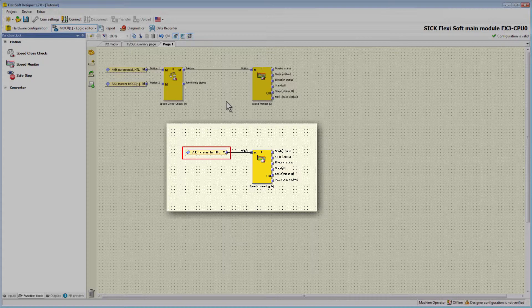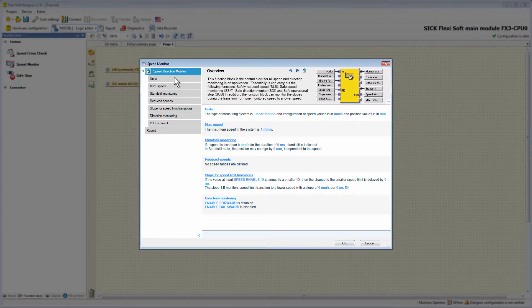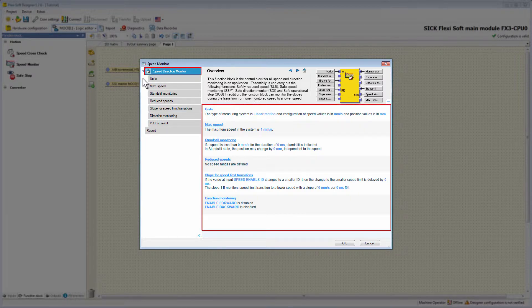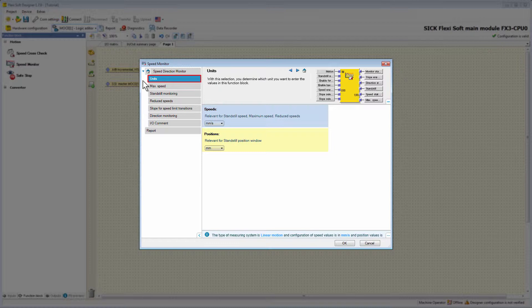If only one encoder is used, the encoder signal can be connected directly to the input Motion of the SpeedMonitor. After the two function blocks are connected, we take a closer look at the configuration. With a double click on the block, I open the configuration menu. The overview page appears showing the current configuration. In the first tab, Units, you have to define the unit relevant for the speed and position values. The defined units must match the motion type of the encoders and the configured unit in the SpeedCrossCheck; otherwise, the SpeedMonitor turns orange and the configuration becomes invalid.